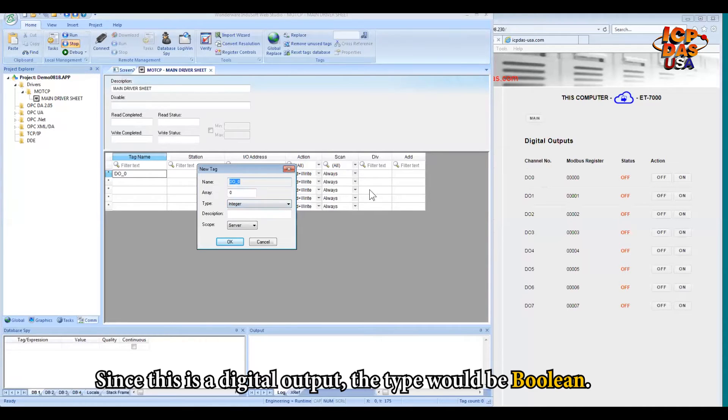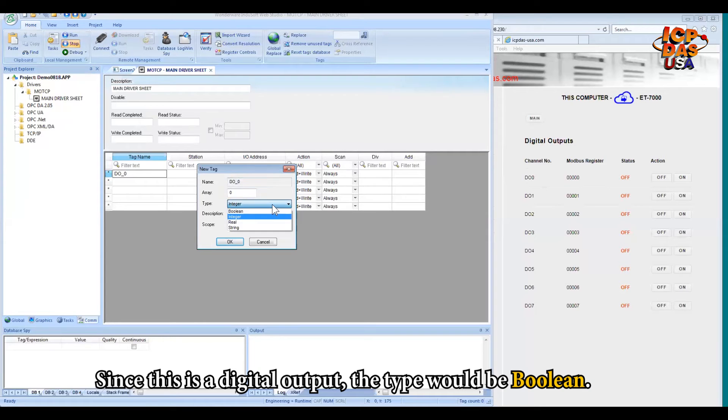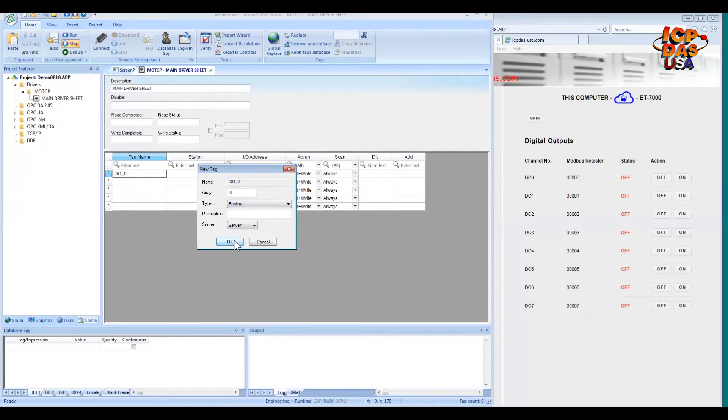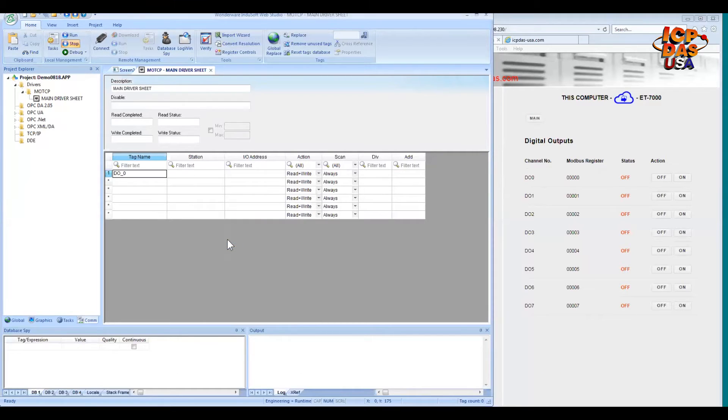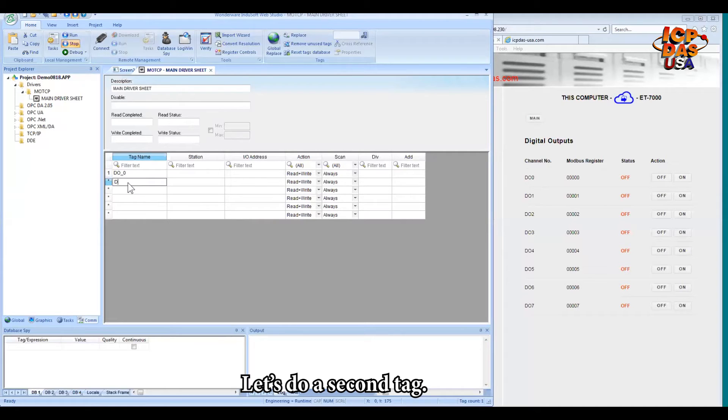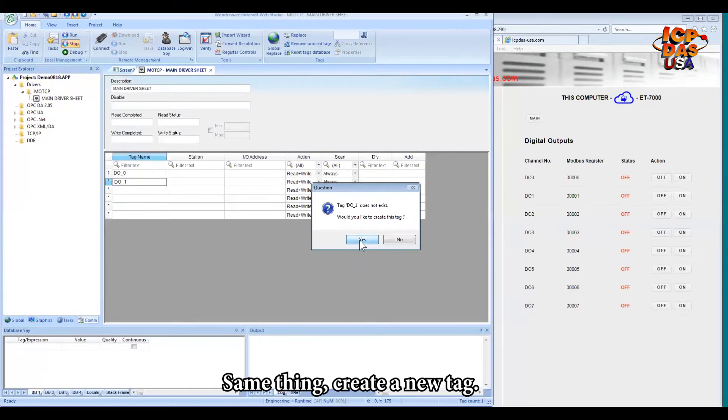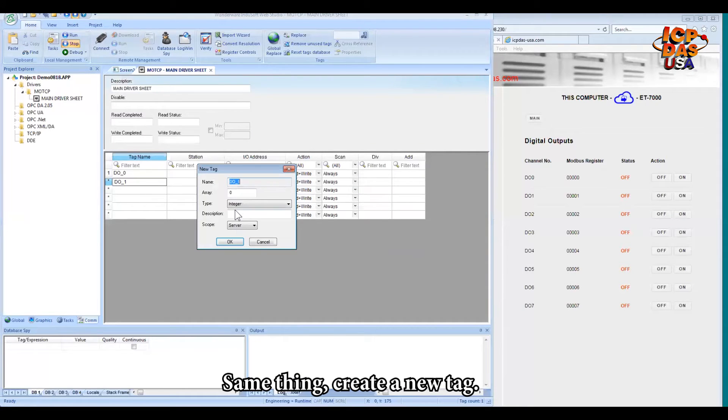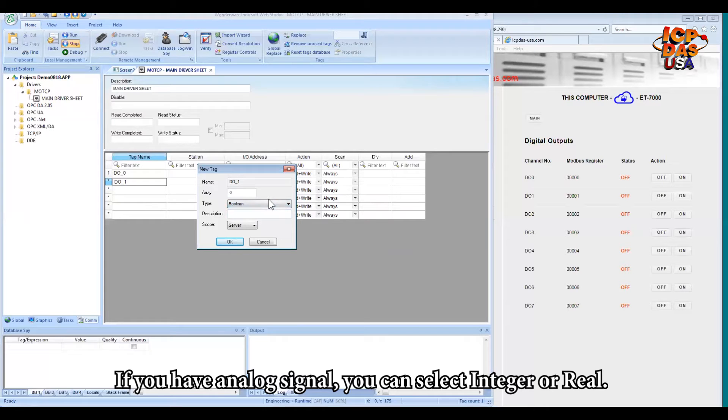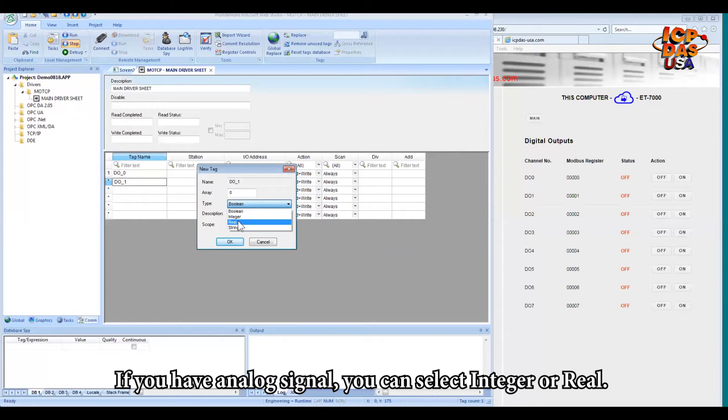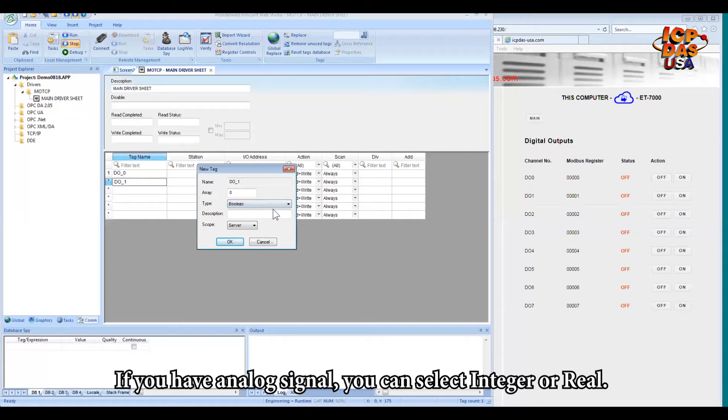So since this is a digital output, the type will be Boolean. OK. Again, let's do a second tag. Same thing. You need to create a new tag and check the Boolean. If you have an analog signal, then you will select integer or real depending on the data type.